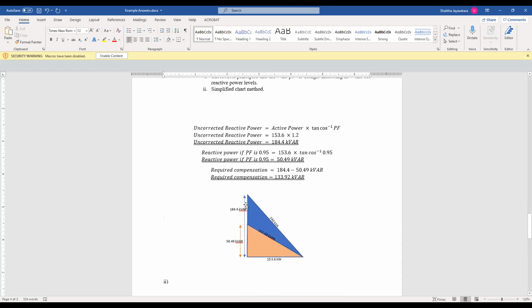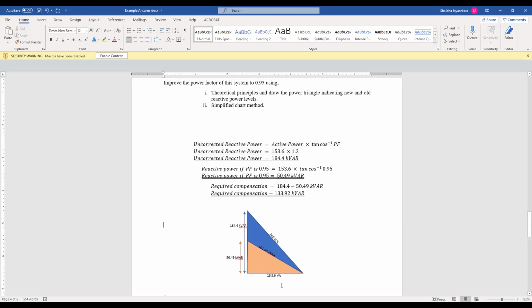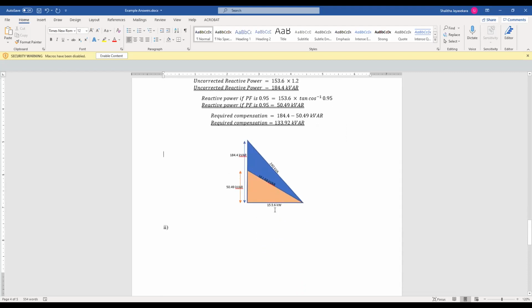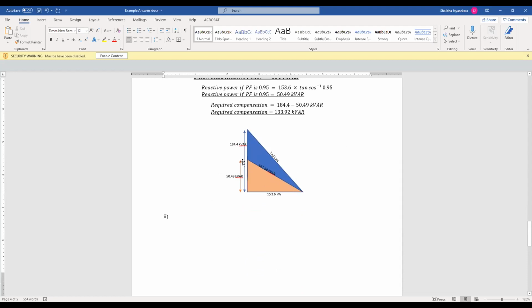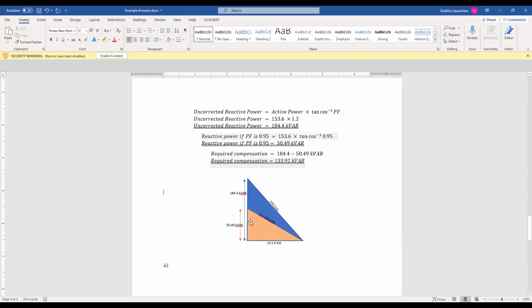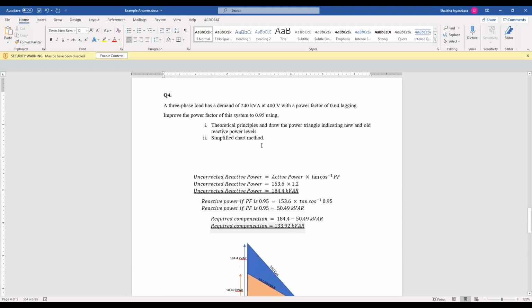In the new system, the reactive power will change. Because of the reactive power change, your apparent power will change. The active power will never change. Okay, so this is how you draw the power triangle. This blue one, the larger one, is the power triangle for the current, or uncorrected, system, and this is the new system. The orientation can be flipped, no worries, as given in the lecture note. Then the next method is the simplified chart method.